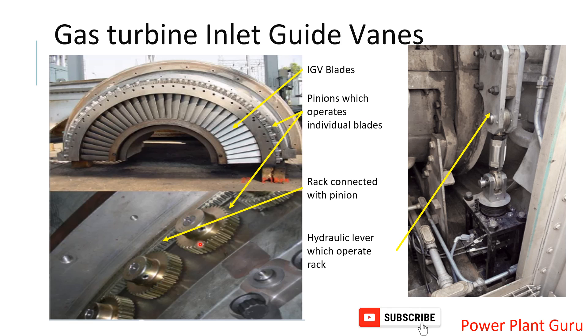These pinions are small gears, individually arranged for one blade each. Every blade has one small pinion, and all these pinions are connected to a rack. This rack, which we can see in the background, is what drives the whole mechanism. The rack moves in both directions to make the vanes close and open.